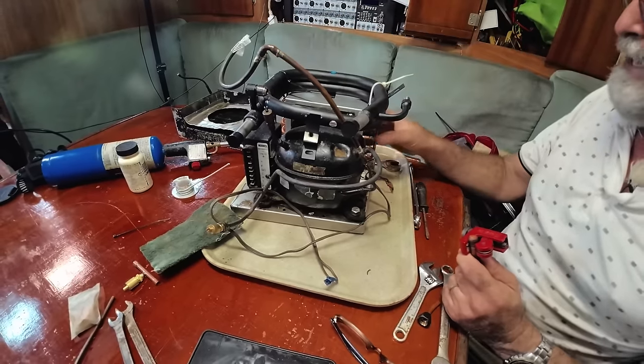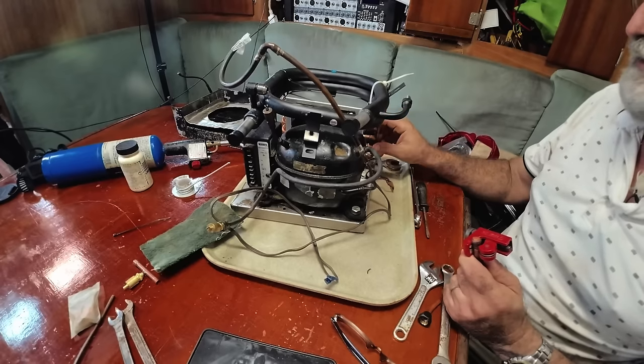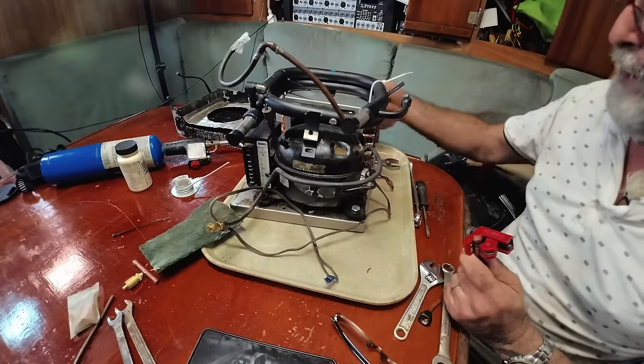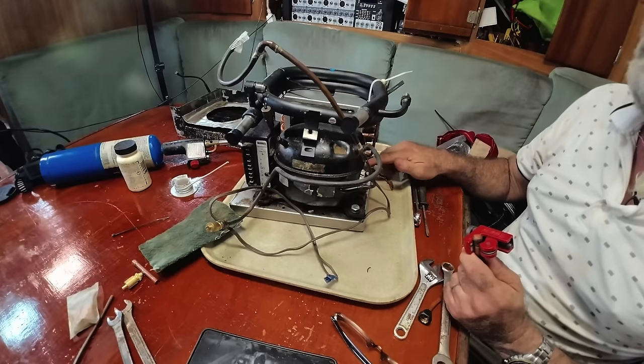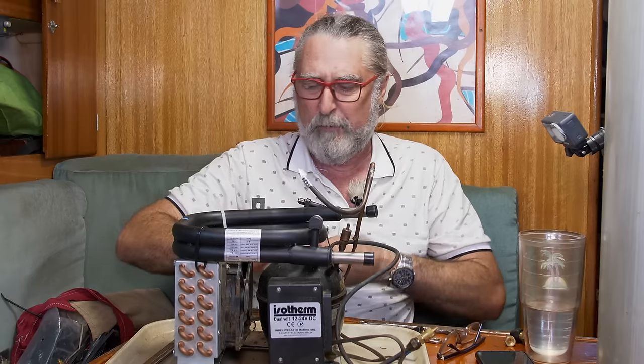And the same here with the air to gas condenser. I'll have the product come in on the top and then go back and forth and back and forth. And then the final liquid will be coming out the bottom. So by the time something falls all the way to the bottom, we're going to be pretty sure it's got into liquid state if it can.